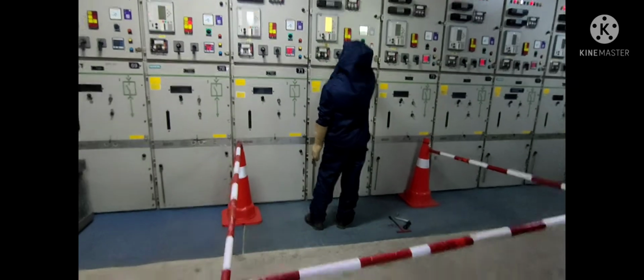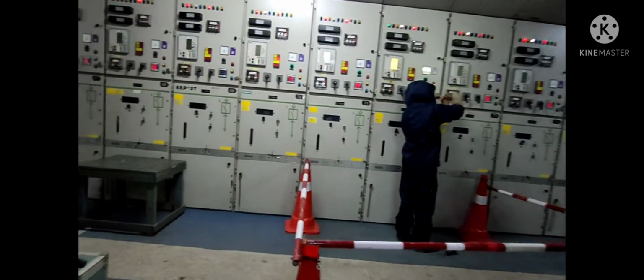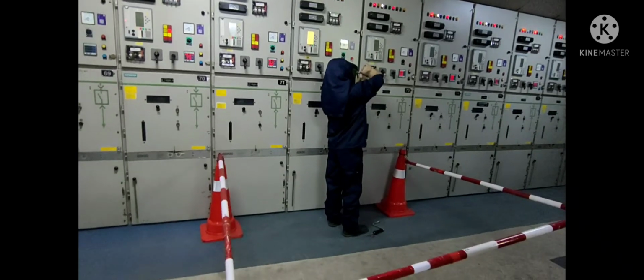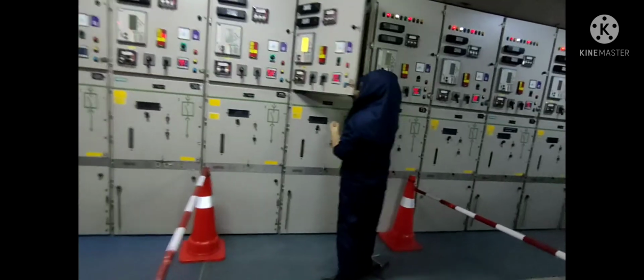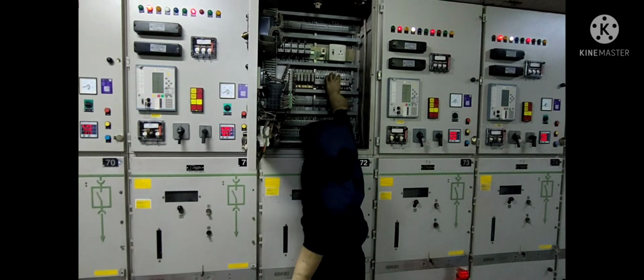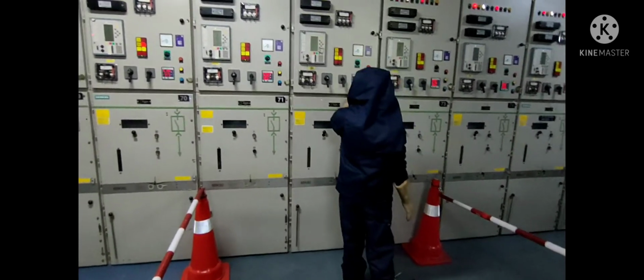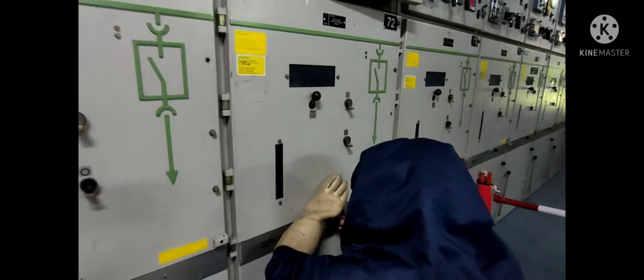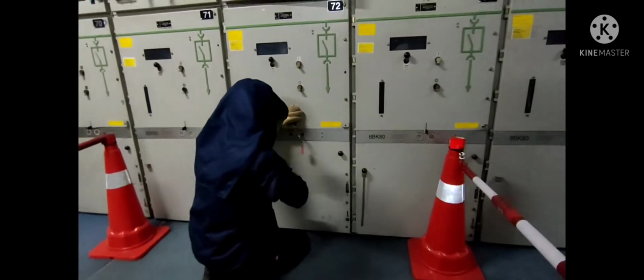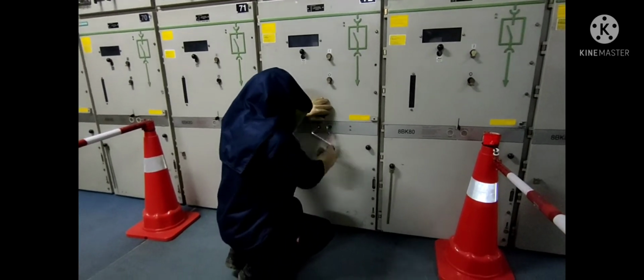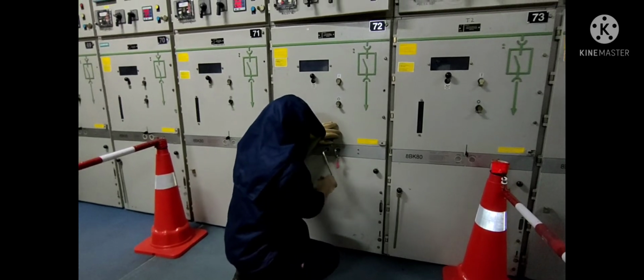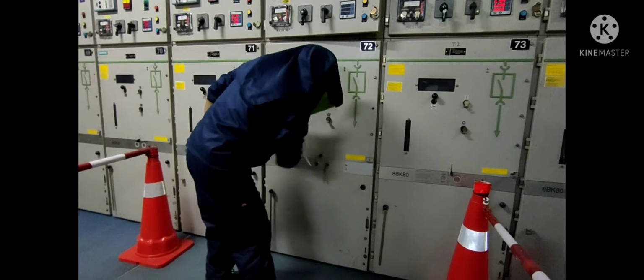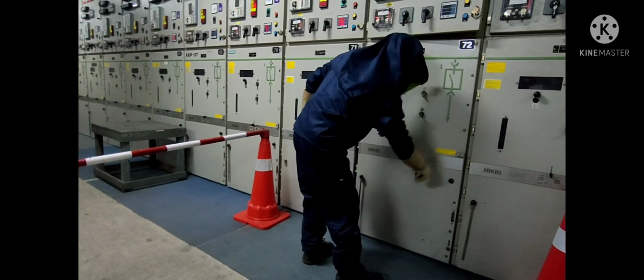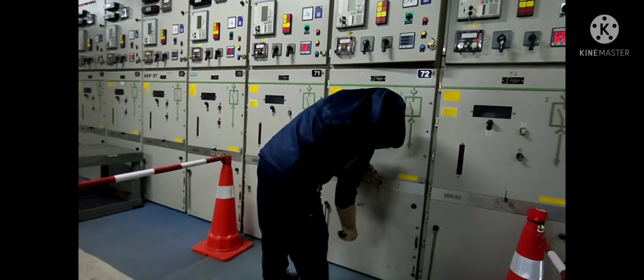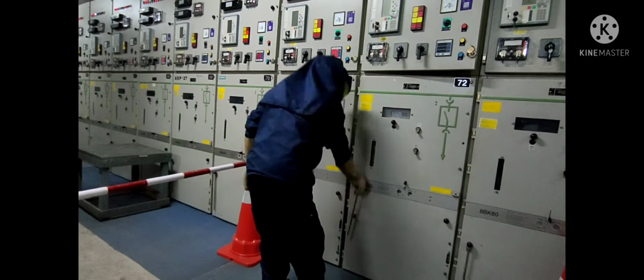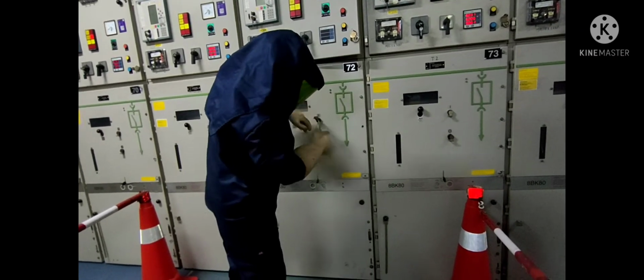Firstly, we have to move the switch from neutral to trip so that we can safely rack out the breaker. In the second step, we will open the control cable chamber with the help of a T-spanner. Now, we have to switch off all the given MCBs. Now we have to insert the key and rotate it anti-clockwise at 90 degrees. After that, we insert the racking handle and rotate it anti-clockwise till it stops rotating. When it comes to the rack out position, rotate the key in the anti-clockwise direction one last time. Discharge the VCB springs with the help of the rod.